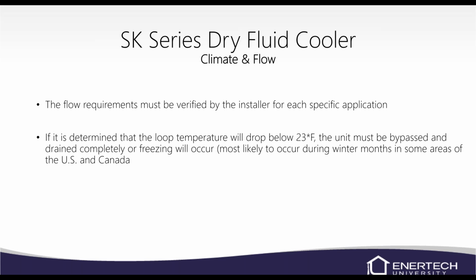If you determine that the loop temperature is going to drop below around 23 degrees, the unit will have to be bypassed and drained completely, or freezing will occur. So if your loop temperature gets below 23, then shut it down, drain it out. It's usually going to happen up in the northern US, Canada, more than likely. So we normally would have freeze protection down to 15 degrees, but we want to give it a little bit of safety factor. So that's why we say 23 degrees.